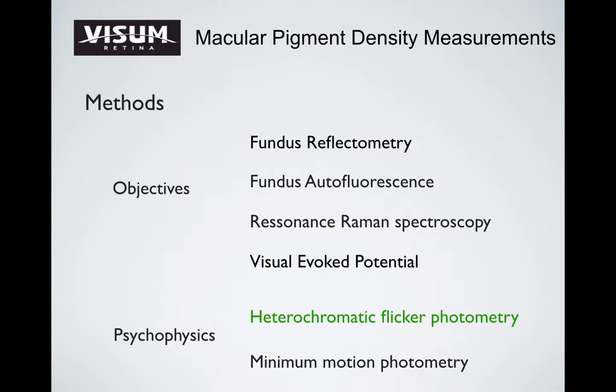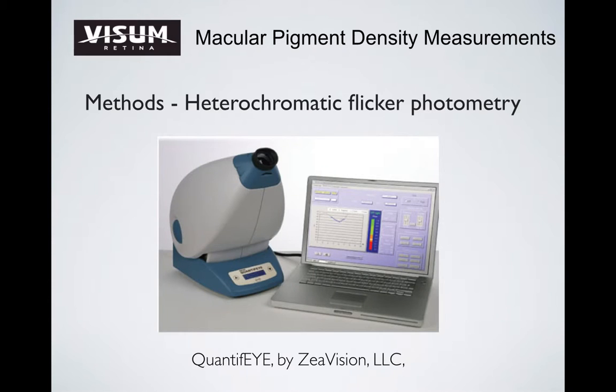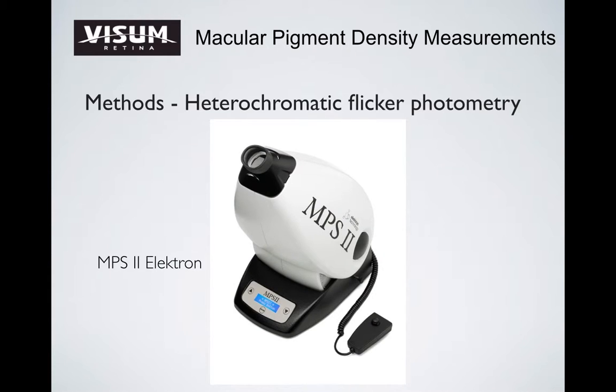The two psychophysics methods are heterochromatic flicker photometry and minimal motion photometry. For heterochromatic flicker photometry, the equipment determines pigment density by presenting a light stimulus of alternating wavelengths until no or minimal flicker occurs. Stronger blue light is required for minimal flicker to reach the receptors. Two pieces of equipment use this technique, including the MPS-2, which is commercially available.